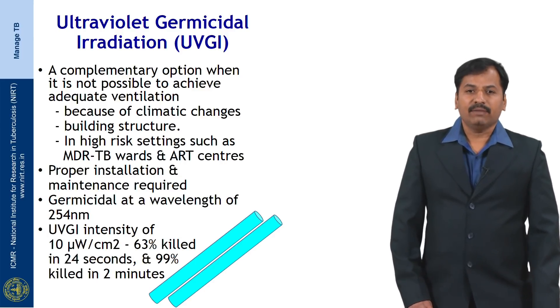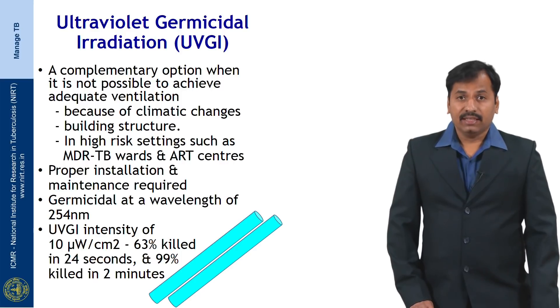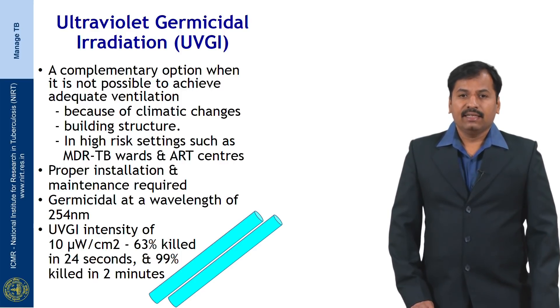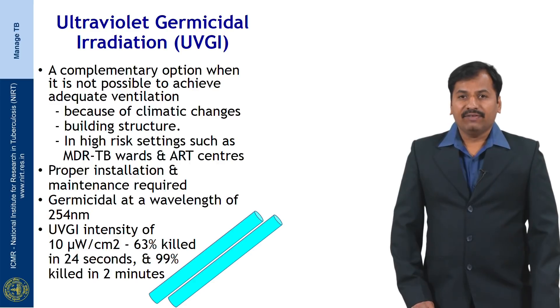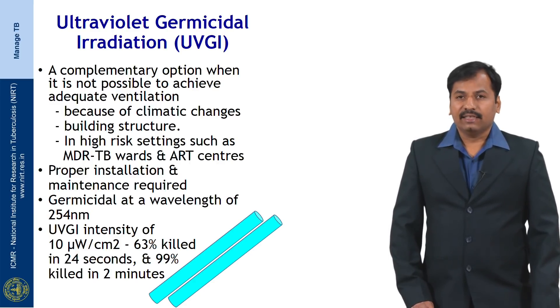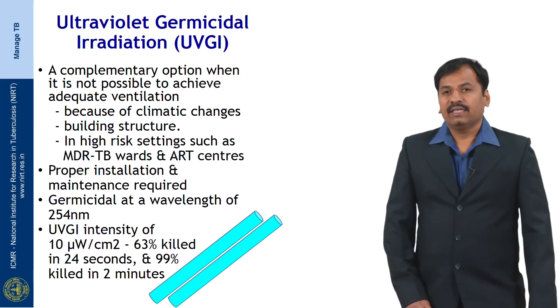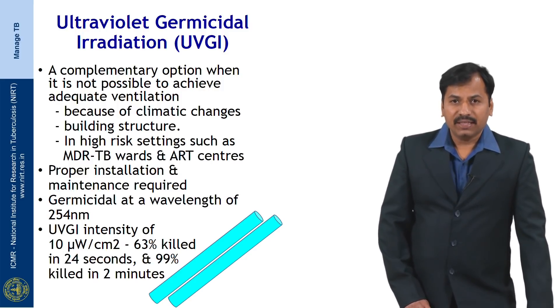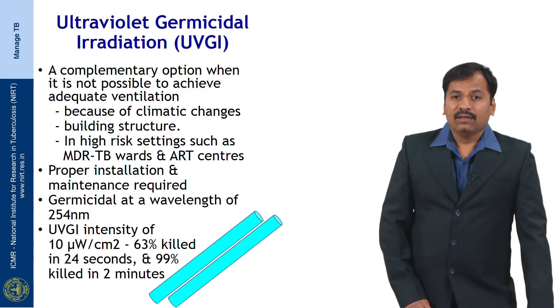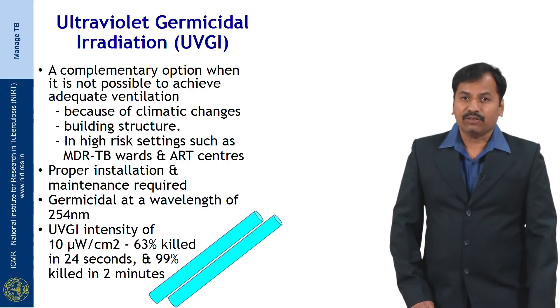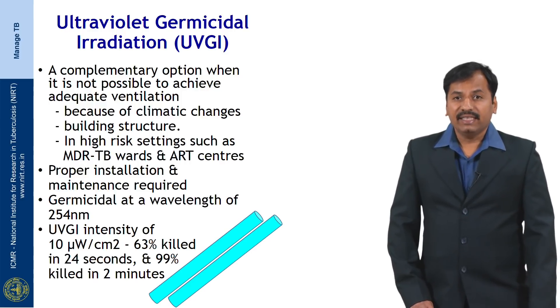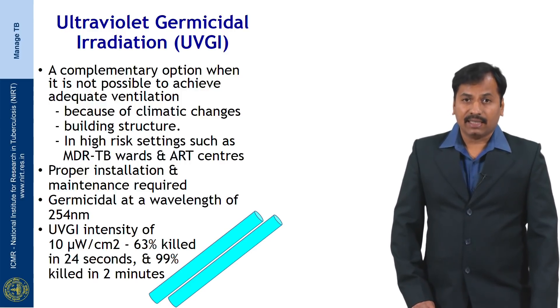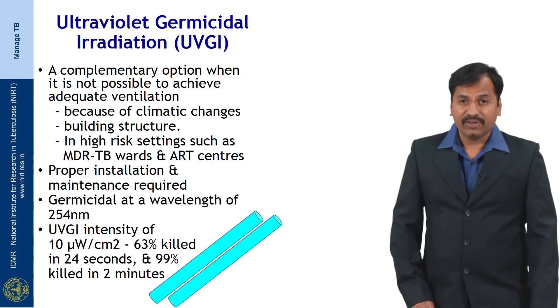Proper installation and maintenance is required if we install this UVGI. Germicidal at a wavelength of 254 nanometers and the UVGI intensity of 10 microwatt per square centimeters for the first 24 seconds kills 63 percent of bacilli, and if continued for the next 2 minutes, 99 percent of the infectious bacilli are killed. So it is a very effective measure that can be implemented in high risk settings.